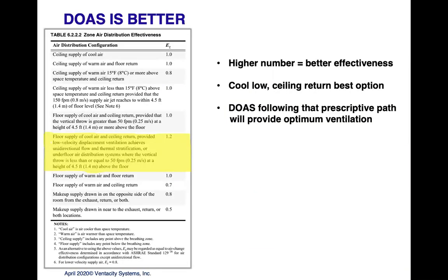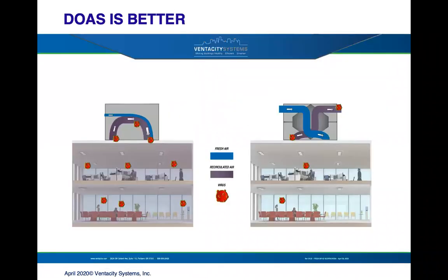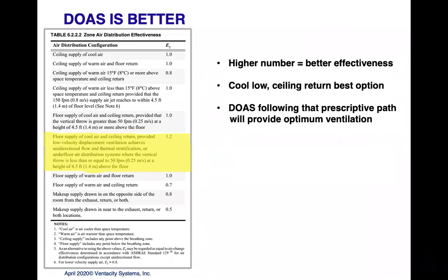One other thing that you can do beyond just putting in a dedicated outdoor air system is to provide optimum distribution of that air in the space. This is the ASHRAE 62.1 ventilation guidance, the air distribution effectiveness chart. And what I've highlighted there, the higher the number for that multiplier, the better that ventilation system is at effectively moving air through, diluting the air in the space and exhausting effectively.